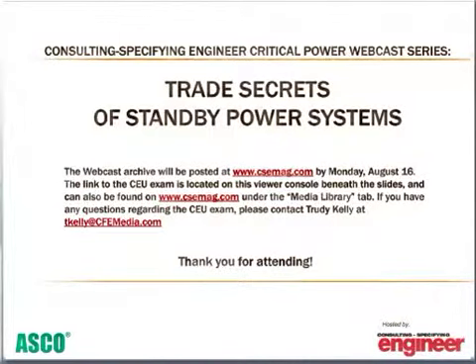Okay. We typically see, if the generators are at 480, we don't see the high impedance grounding system or low impedance grounding. In the 15 kV size, that's when you start seeing the high impedance grounding system. It's for protection of the generator, and what it does is, if there is a fault, it allows you to have an alarm and not trip your system. There's higher end engineering involved. You have to ensure that, for instance, your impedance is not greater than your charge current of your system. Your transient voltage surge suppressors will work differently. So we've seen it both ways in the higher end, tier 3, tier 4 type data centers utilizing 13.2 or 12.47 generators. We've seen the high impedance grounding systems, and they certainly do have their advantages.